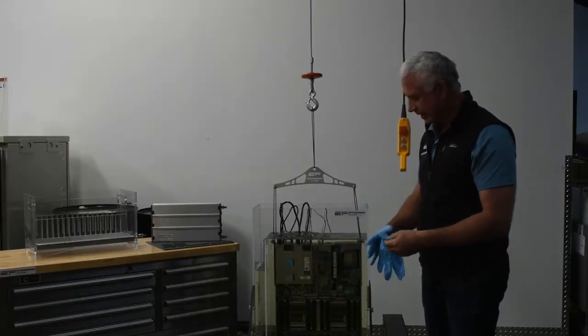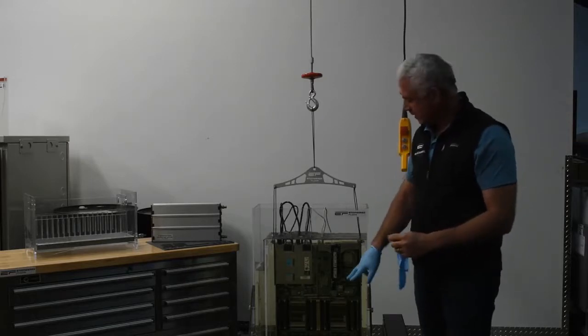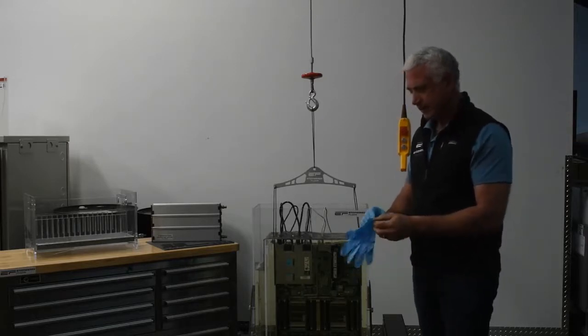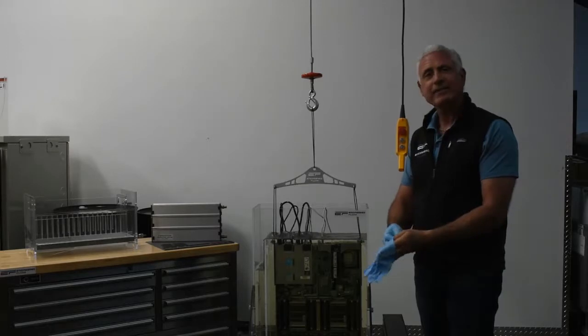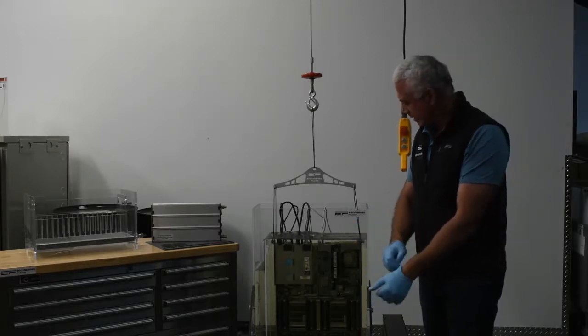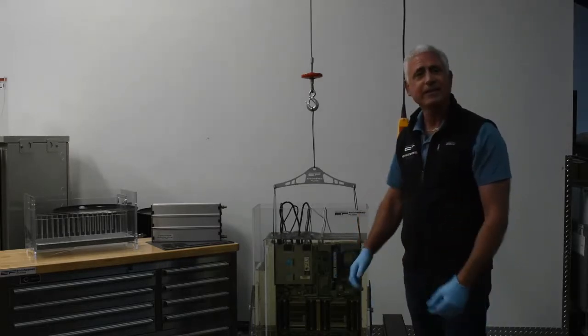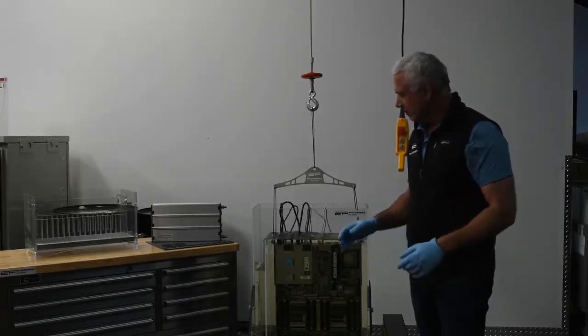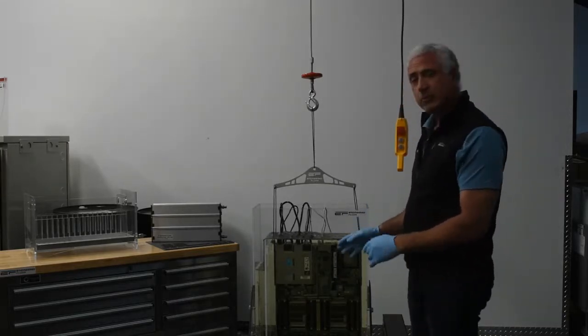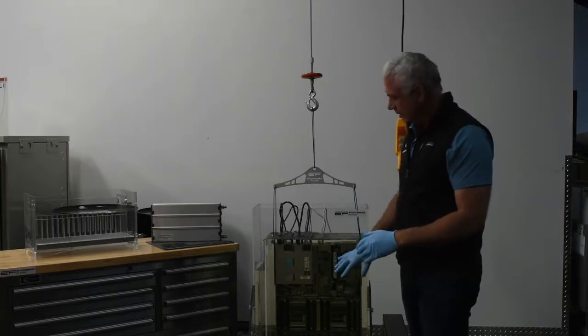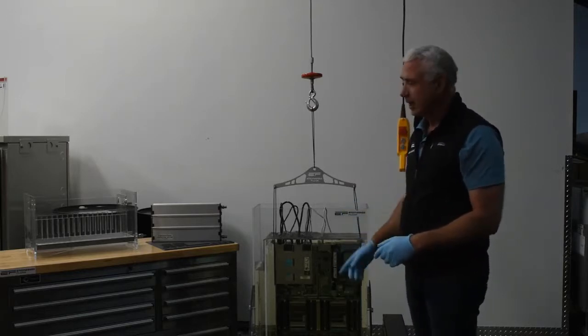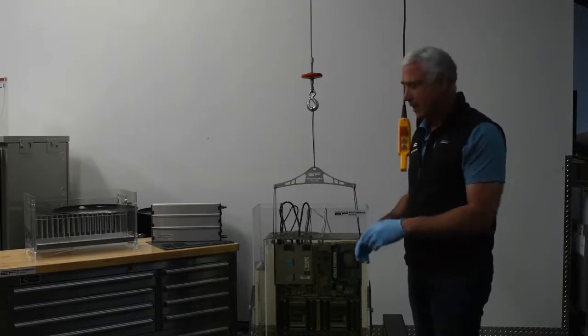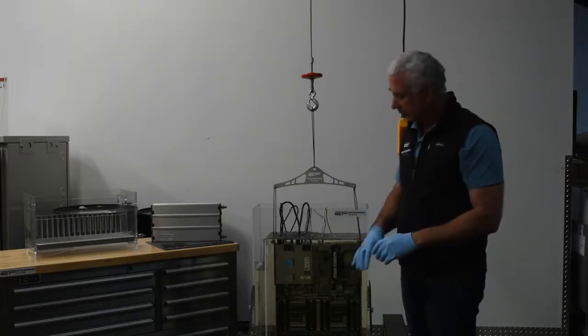Today we've got an HP server. It is in a clear plexiglass test unit that we use here at the lab and the coolant that we have in here today is EC100. So what I'm going to do today is show you the process that we use here at the lab in order to remove the server, then replace the memory chips and then place it back in.